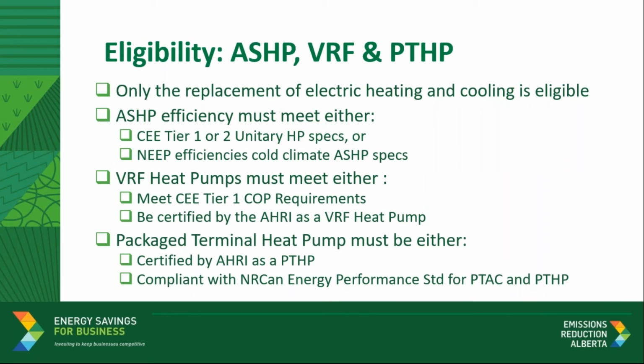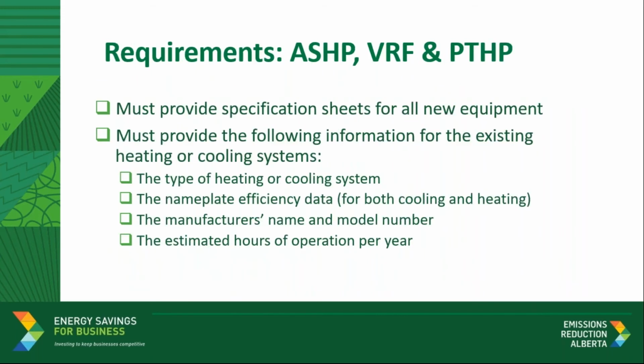In terms of efficiency, it is required that the air source heat pumps meet either the Consortium for Energy Efficiency (CEE) Tier 1 or 2 for unitary heat pumps, or the Northeast Energy Efficiency Partnerships (NEEP) specifications for cold climate air source heat pumps. Similarly, the variable refrigerant flow heat pumps must meet the CEE Tier 1 COP requirements, or they must be certified by AHRI as a variable refrigerant flow heat pump. For packaged terminal heat pumps, they must be certified by AHRI, or they must comply with the NRCan Energy Performance Standard for PTAC or PTHP, or packaged terminal heat pumps. As a reminder, this group of measures is only eligible when replacing electric heating and cooling.